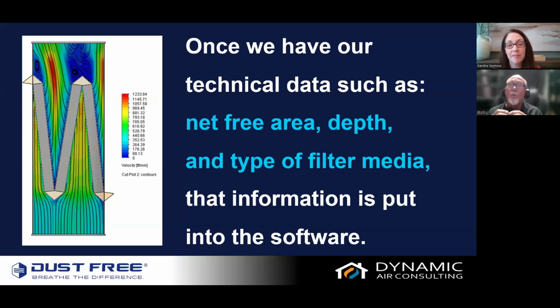Then we look at what air does in a duct system. We have the fan driving the airflow, we have velocities, resistance, and static resistance for the amount of ductwork it's going through. But there's also something called vena contracta, which happens when air is going through, say, a round duct, and then changes direction into a long rectangular shape or a square filter housing.